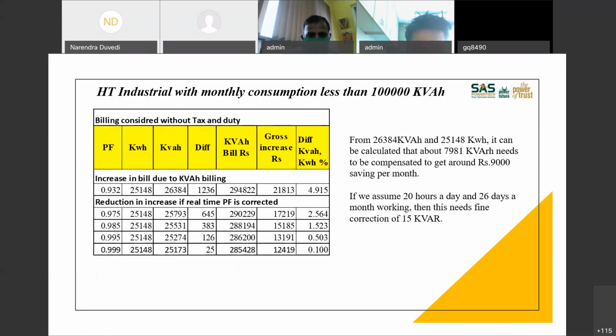And if he tries to correct his power factor, say presently his power factor was 0.932 as mentioned here, if he tries to go to 0.999, there will still be some difference in the bill because of the basic increase in the tariff itself. And if you calculate here, if you really want to compensate for that marginal difference between kVAh and kWh, you will have to closely control about 15 kVAR in his factory. If he is working 20 hours and say 26 days a month, controlling 15 kVAR very closely is comparatively difficult, probably possible only with electronic corrections. And the payback may or may not be attractive because with all that, he will save only 9,000 rupees a month. So this is what I call economics. We will come to know more about this later. But these calculations one will have to make.